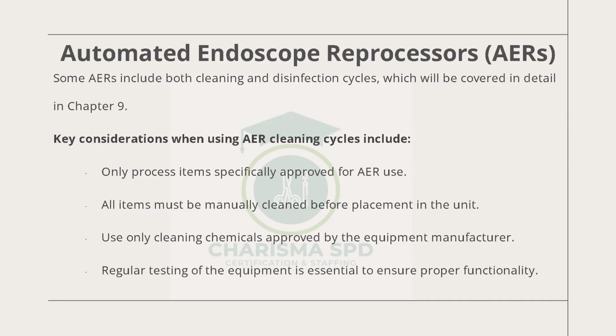Okay, they include some of them. As I said, we do that by just hand washing, and we use special sponges for it. But for those that have the machine for the automated one, there are key considerations when using this automatic endoscope reprocessor. If you don't have it there, it's a different thing. But if you have it, you have to pay attention to these key considerations. Only process items specifically approved for the automated endoscope reprocessors. Don't put anything else. All items must be manually cleaned before placing them into that unit.